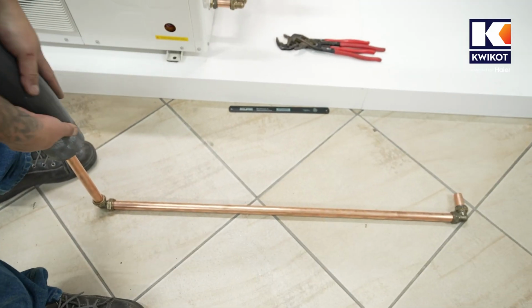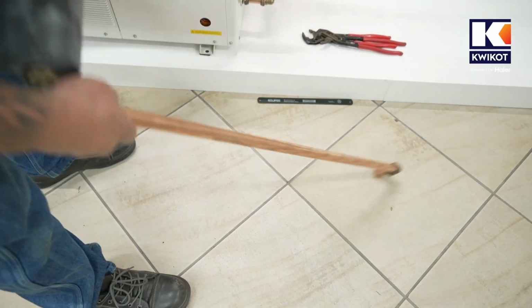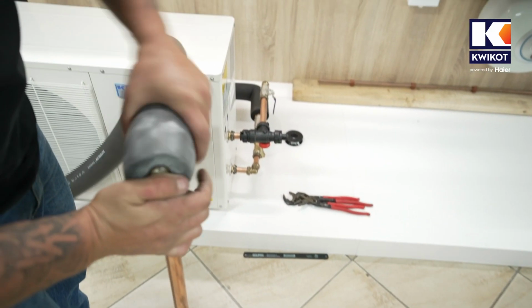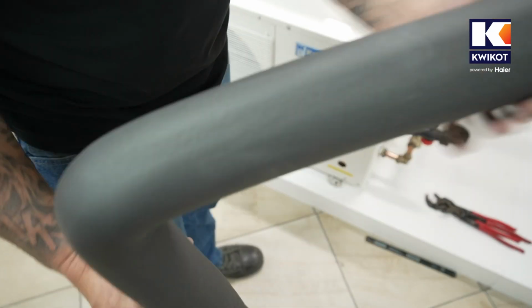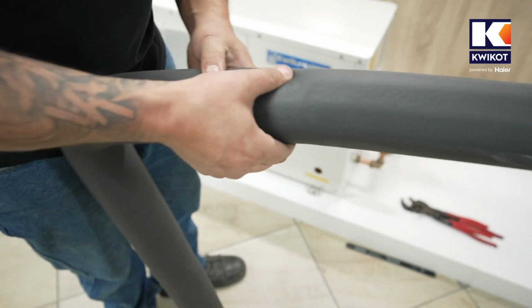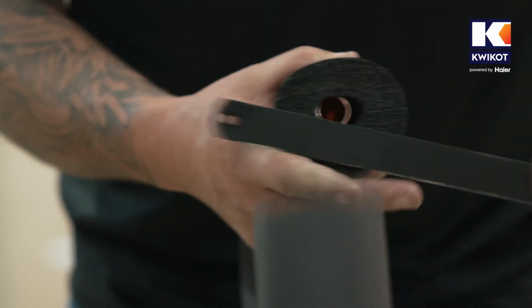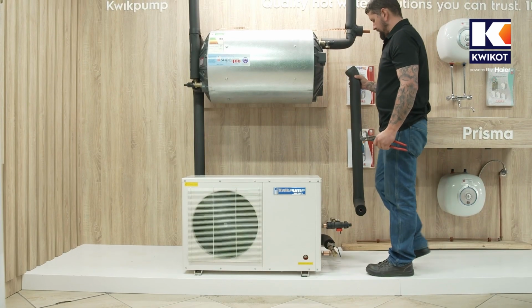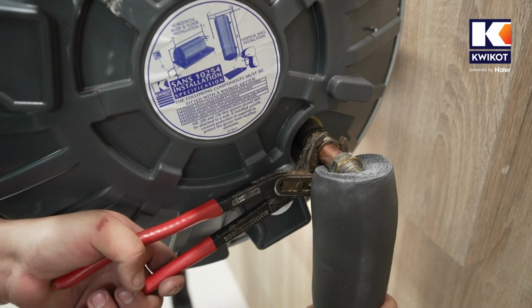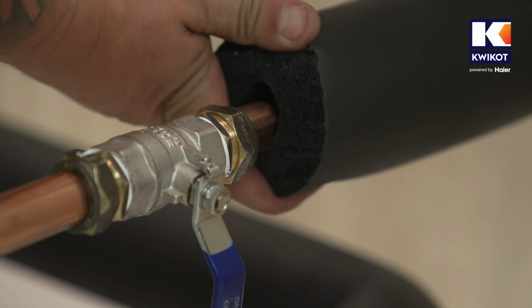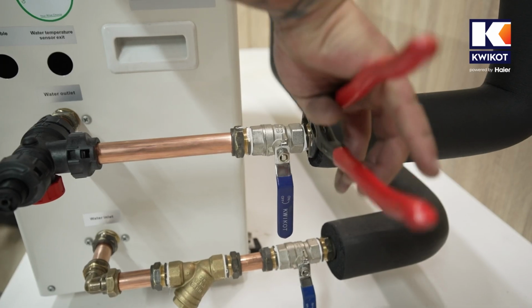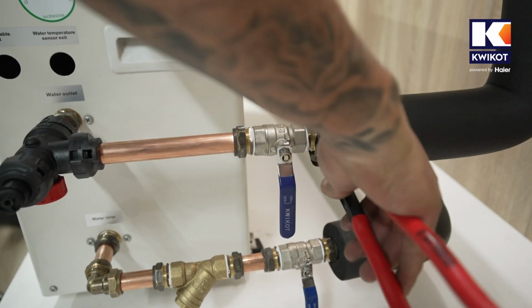Now we're going to remove the last 3 lengths of piping in one piece in order to fit our lagging. We trim off this piece of lagging after feeling where the pipe is. And then we can refit it to the renewable port. Then we will refit the lower end of the pipework into the ball valve at the bottom.